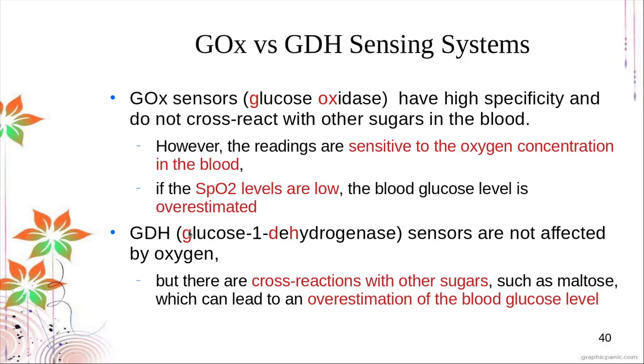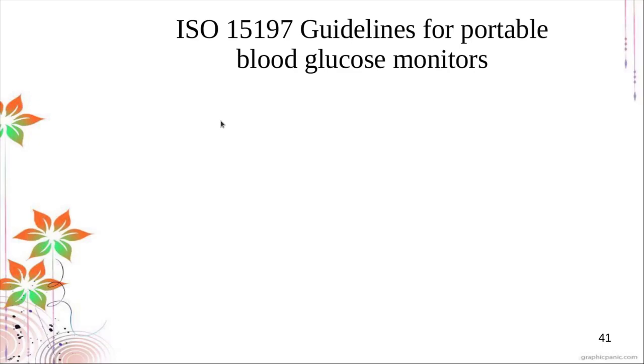In the Philippines, the most common is the GOX sensor. Because it is sensitive to oxygen, the usual practice is to measure SpO2 levels first and then perform glucose monitoring. If you have low SpO2, it is not advisable to use the GOX sensor. Glucose sensors are prevalent due to the prevalence of diabetes, and we have ISO 15197 guidelines for portable glucose monitors.